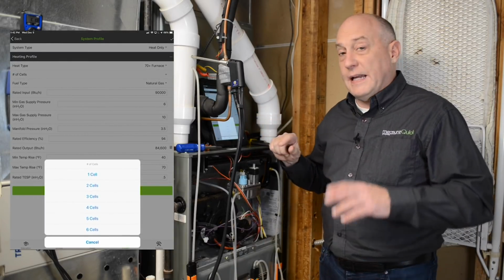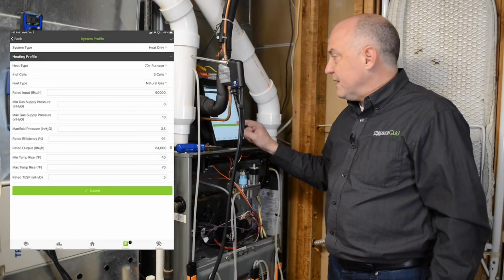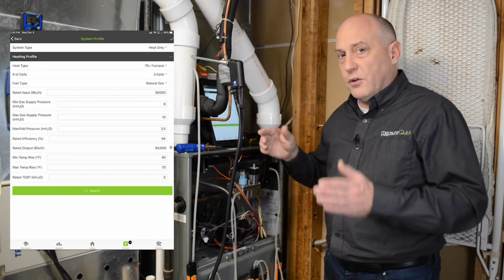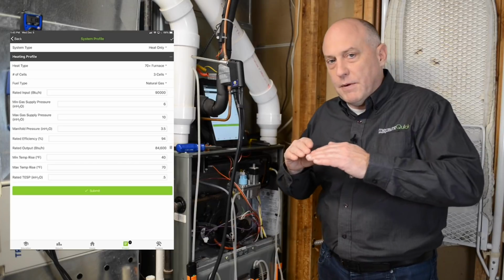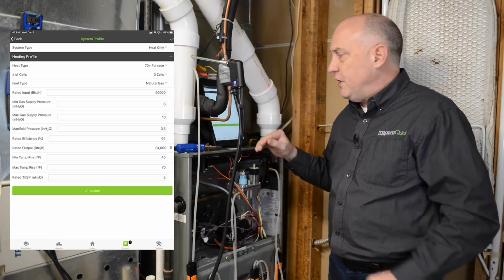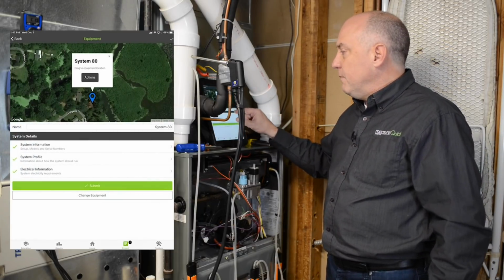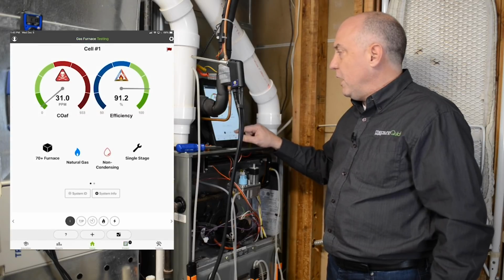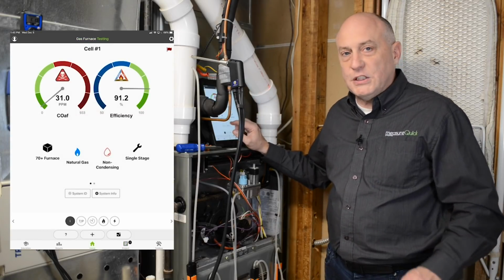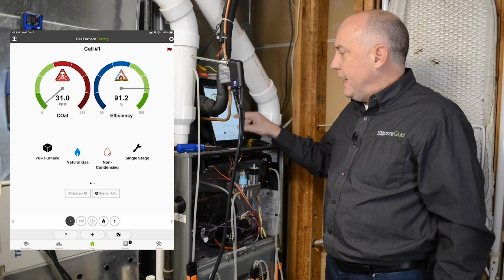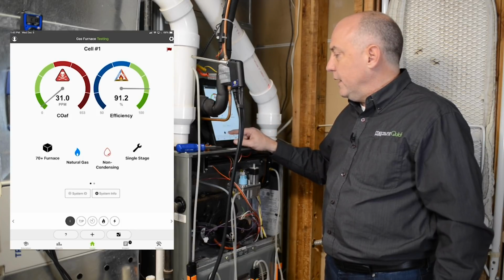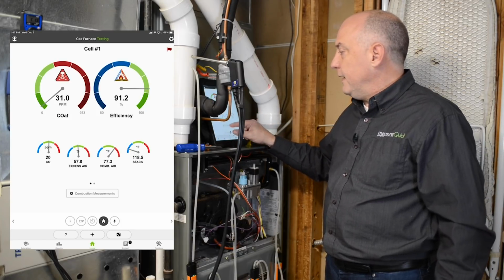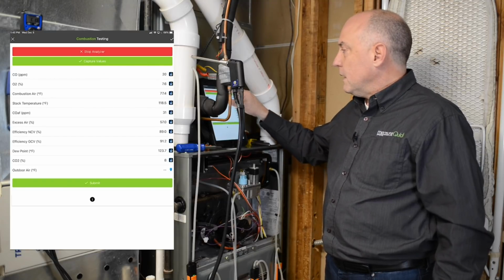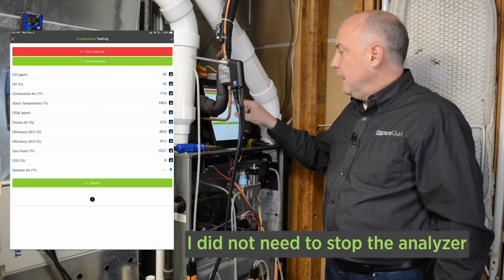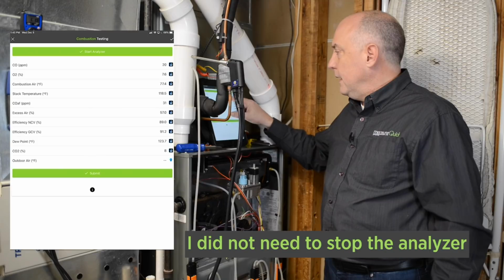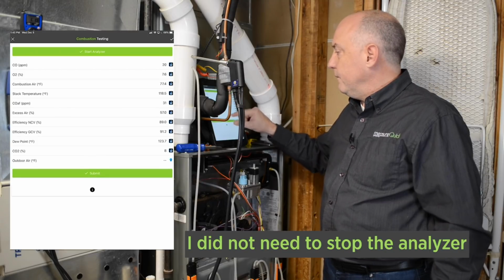Well, now we can actually capture the number of cells. So in this case, I hit 3 cells on there, a 3-burner furnace, and when you're doing a combustion test, each one of those needs to be checked individually. So now when I hit submit on here and hit submit again and go to my home screen, you can see at the top now I have cell number 1. So if I tap on that and I do my combustion test, I'll go into combustion measurements here for just a minute, hit combustion, I'll stop the analyzer, and let's see here, actually let's hit submit.